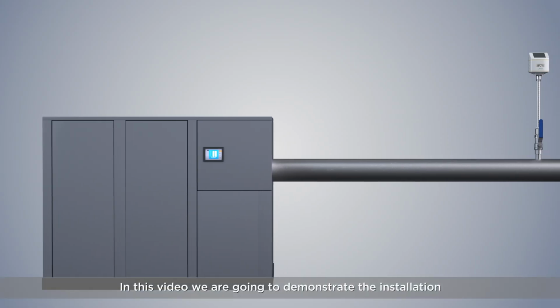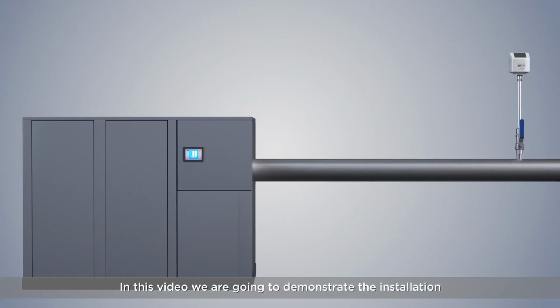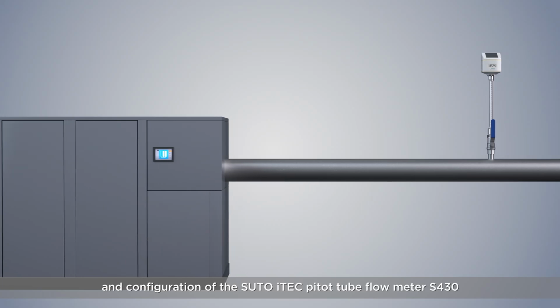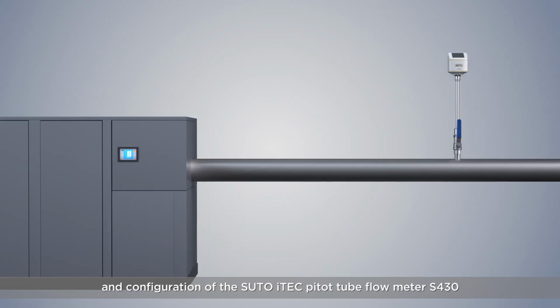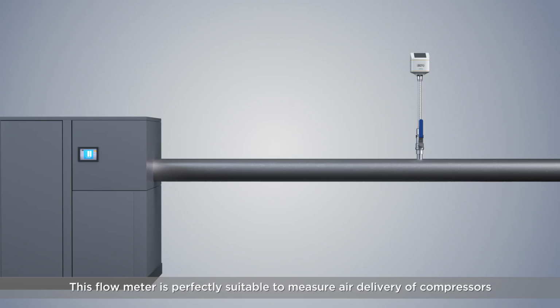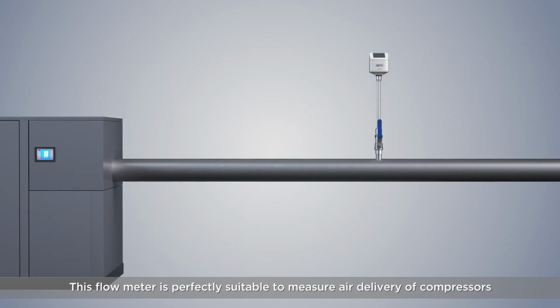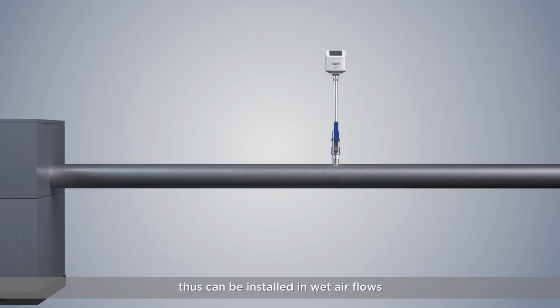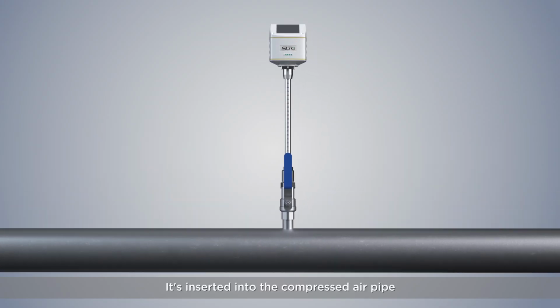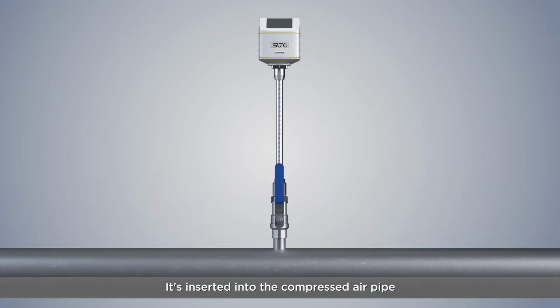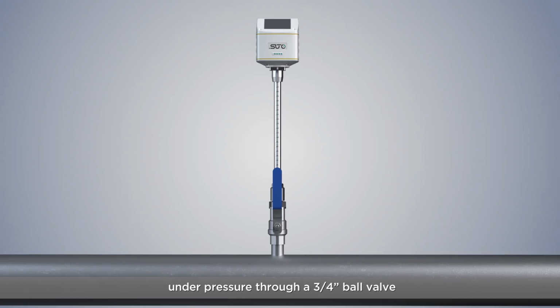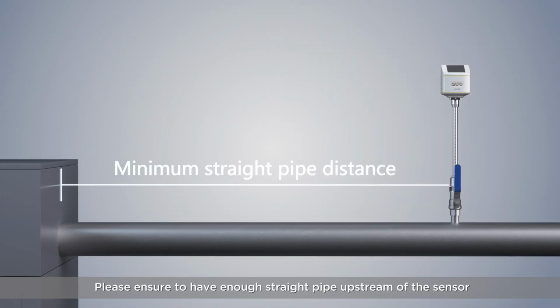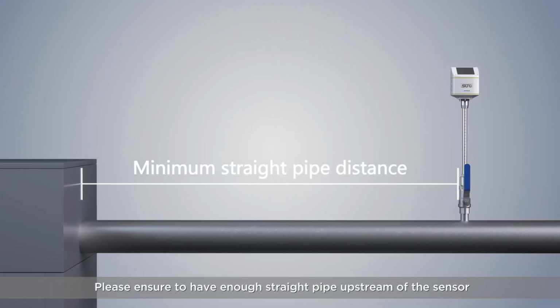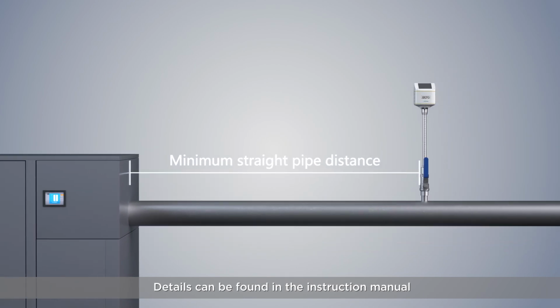In this video, we are going to demonstrate the installation and configuration of the Suto iTEC Pitot Tube Flow Meter S430. This flow meter is perfectly suitable to measure air delivery of compressors, thus can be installed in wet airflows. It's inserted into the compressed air pipe under pressure through a 3/4 inch ball valve. Please ensure to have enough straight pipe upstream of the sensor. Details can be found in the instruction manual.